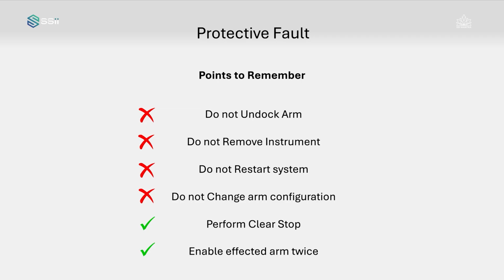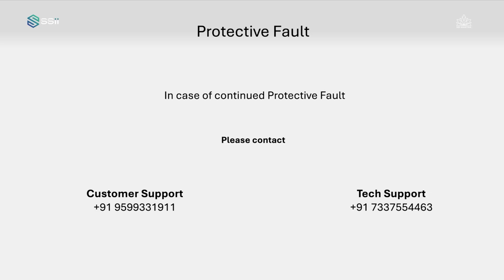Use the amber highlighted clear fault button on the SCC 2D control screen or the amber color clear fault button on the SCC control panel to clear protective fault. Enable the affected arm twice post clearing the stop. In case of continued protective fault occurrence, please contact our tech support team for further assistance and resolution.